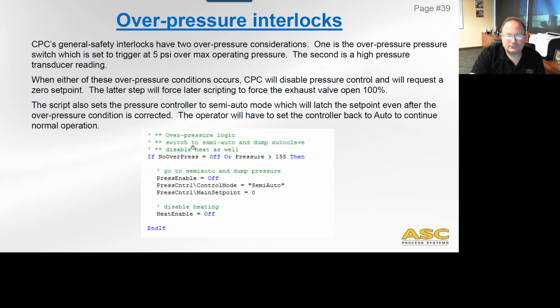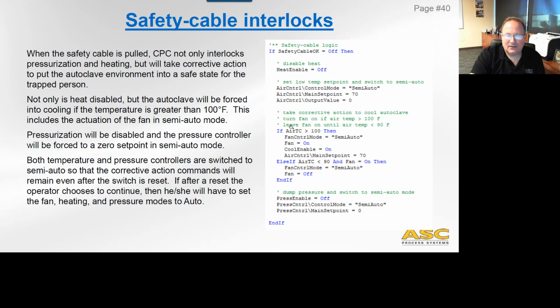So that's a little bit different than the normal logic that we've seen. The safety cable interlocks. When the safety cable is pulled, CPC not only interlocks pressurization and heating, but it will take corrective action to put the autoclave environment into a safe state for the trapped person. So not only is the heat disabled, but the autoclave will be forced into cooling if the temperature is greater than 100. This includes actuating of the fan and putting it in semi-auto. And so pressurization will be disabled and the pressure controller will be forced to zero set point, and semi-auto, again, latching it to go all the way to the bottom.